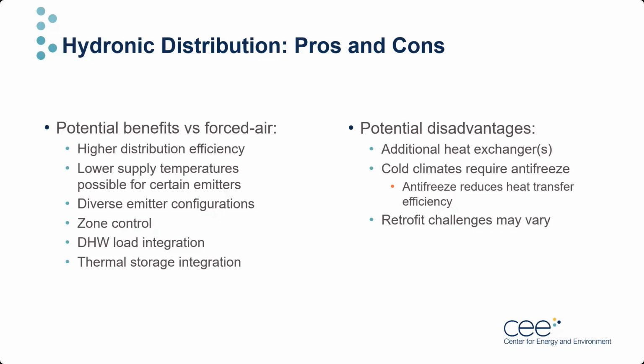Potential disadvantages to this include the addition of a refrigerant-to-water heat exchanger, like we saw in our schematics, that would introduce a new source of potential inefficiency. And one that's pretty relevant to our climate is the need for sufficient protection against the hydronic lines freezing and bursting. This is not new to hydronic systems, but it is not a consideration with traditional air source heat pumps that just use refrigerant and air. The addition of antifreeze like glycol will reduce the heat transfer efficiency of the hydronic fluid, and the sites we monitored included the addition of between 25 and 50% glycol to the water loop.